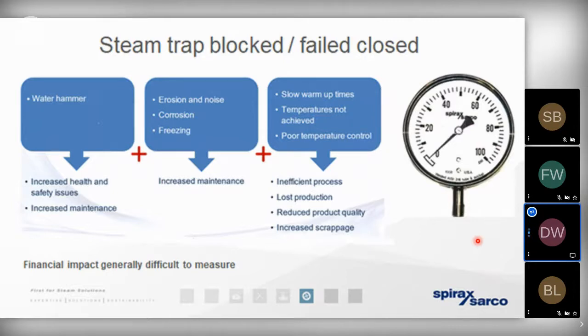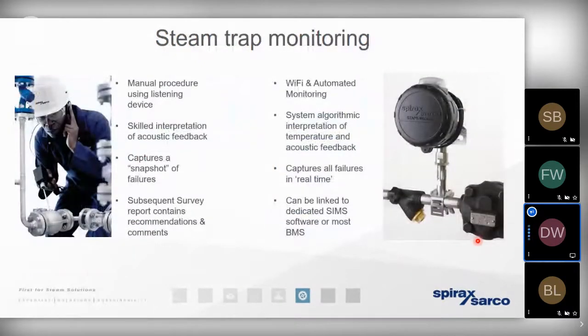And over time, that condensate could back up and start to flood the distribution network. And it's at that point that we get the erosion, the corrosion, the water hammer. It's at that point that we find we get a greater heat loss and there's less and less energy present within the steam. So again, just to reiterate, that steam trap audit, the steam trap monitoring is critically important. I suppose the major difference is if we're able to undertake a periodic manual audit, we're able to determine that the trap has been sized, selected and installed correctly, as well as demonstrating a payback if and when we're able to repair that trap.